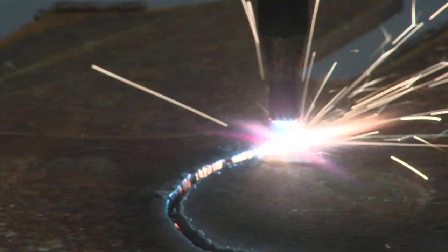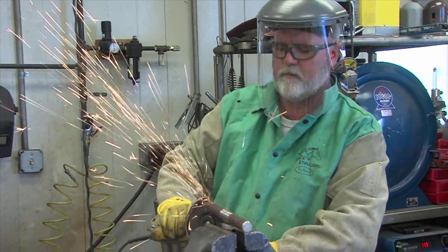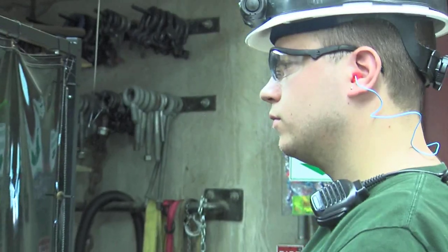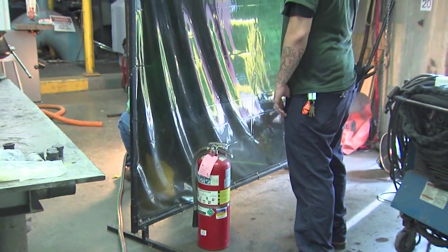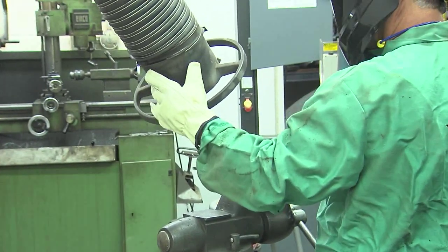Prior to hot work — which includes welding, cutting, burning, heating, or any work involving open flame — the contractor will notify their PIC and get a hot work permit. The control room operator and operations personnel will identify the job location, the type of work being done, and what safety precautions the personnel must take. When cutting or grinding any type of material, a face shield shall be worn. In the event that a small workspace restricts the use of a face shield, then goggles shall be worn. Anytime welding is done near another worker, contractors are responsible for supplying adequate shields and curtains to protect passers-by. If hot work is being performed near flammable material, the contractor will be required to supply a fire watch. This fire watch must be posted during all activities and also for up to a 60-minute post-work period. When using a torch, a backflow arrester must be installed. When welding chrome or stainless steel, the contractor must have a hexavalent chrome program in place.